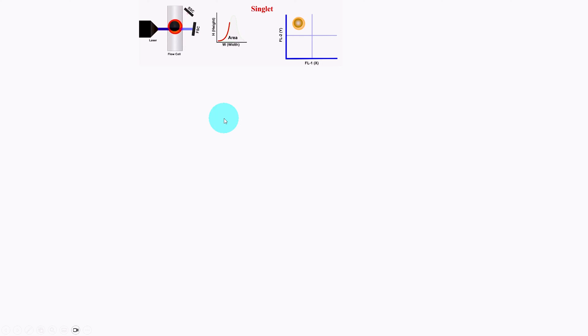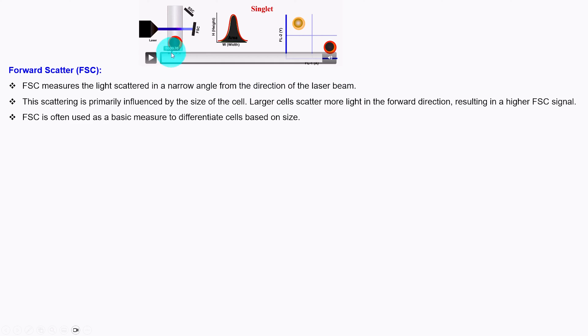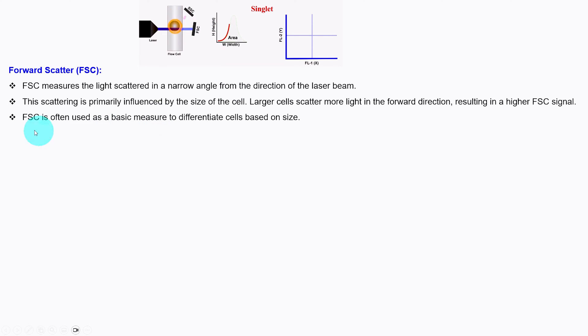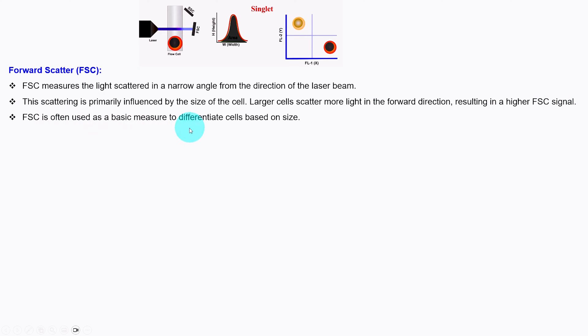The first parameter is forward scatter, FSC. FSC measures the light scattered in a narrow angle from the direction of the laser beam. This scattering is primarily influenced by the size of the cell — larger cells scatter more light in the forward direction, resulting in a higher FSC signal. FSC is often used as a basic measure to differentiate cells based on size.